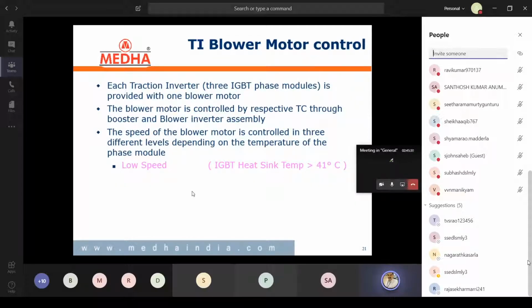If the inverter temperature is up to 40 degrees, the blower will be completely in off state. If the inverter temperature is more than or equal to 41, the blower starts running at low speed, at 48 medium speed, at 55 high speed. There is a small inverter inside that generates a low voltage signal to drive this blower at 3 different speeds: low speed, medium speed, high speed, based on the inverter module temperature. Okay, so 3 speeds.